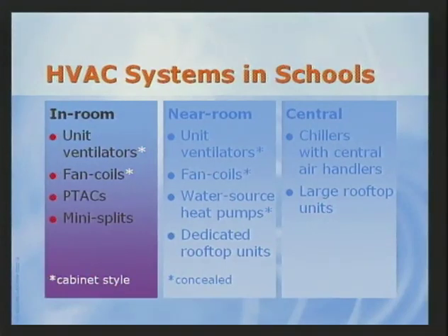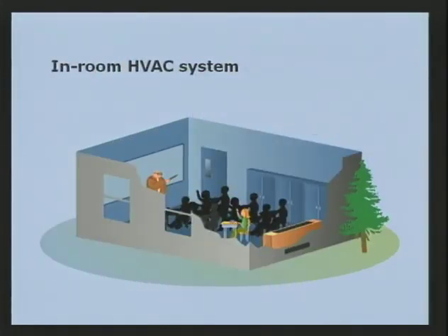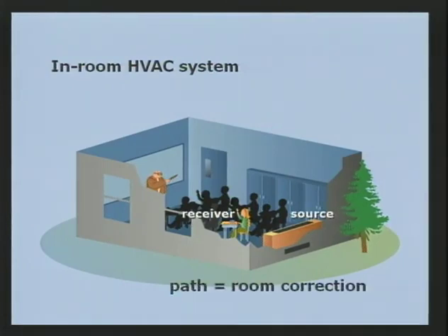Products in this category include cabinet models of unit ventilators and fan coils, PTAC units, and mini splits. For source data, start with the total octave band sound power data for the unit. The path for in-room products is just the space between the unit and the receiver. Essentially, this amounts to the room correction being the path. Perhaps the simplest way to look at in-room units is to work backwards, starting with the 35 dBA requirement and adding room correction to determine the required unit sound levels.